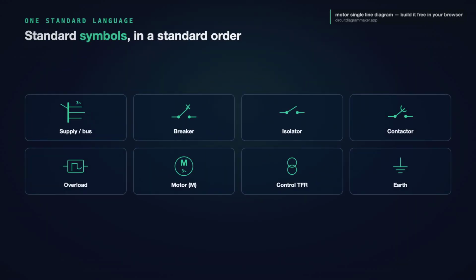Standard symbols in a standard order. A bus bar for the supply, a switch with a cross for the breaker, a plain switch for the isolator, a switch with an arc for the contactor, a little block for the overload, a circle M for the motor, 2 circles for the control transformer, and earth reaching all of it. That is the whole language of a motor single line diagram. And it is exactly why the drawing exists, because anyone who knows these symbols can pick up your page and read the entire starter without ever opening the panel.